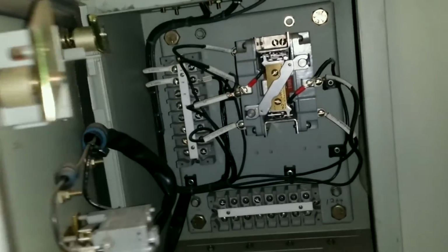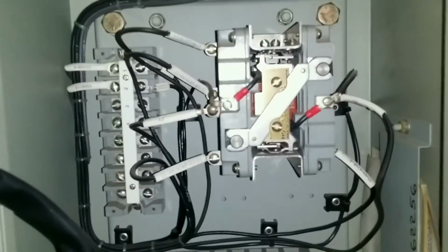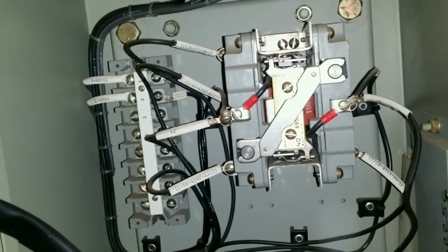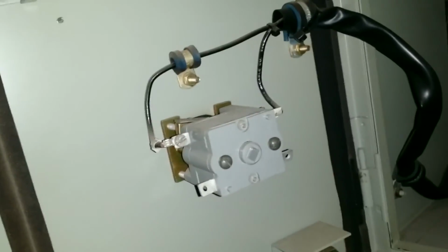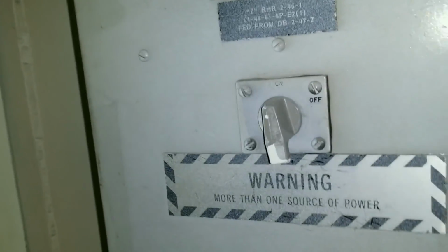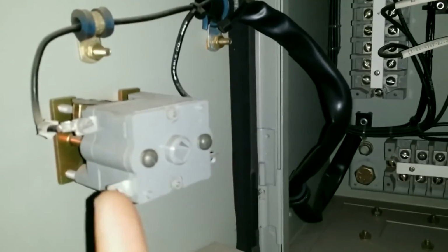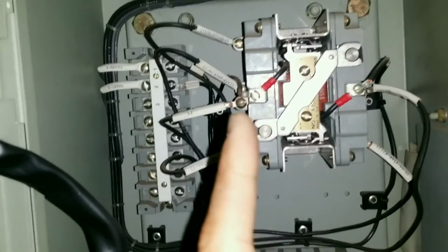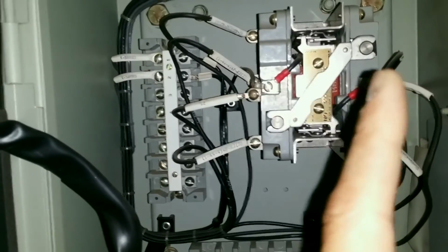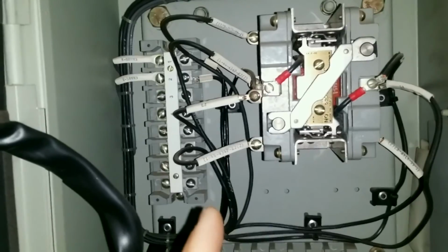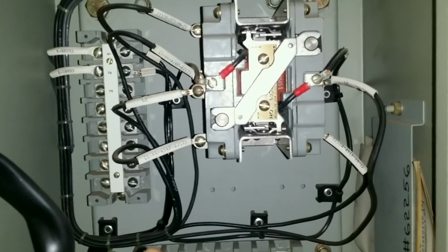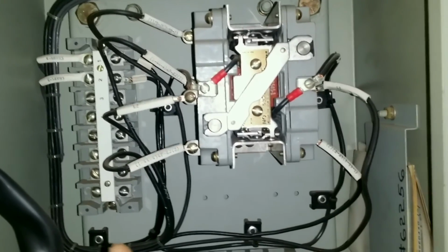Reheater controllers typically have only one contactor, which is to energize the actual heater, a little terminal board, and the on and off contacts for the switch. The control side coils receive the 110 volts, obviously when this switch is closed and when the other permissions are met. In the back, we've got 440, where the L leads are on top, and at the bottom is where the heater is. The contactor bottom connections that go to the heater are a great place to check resistance of the heater.